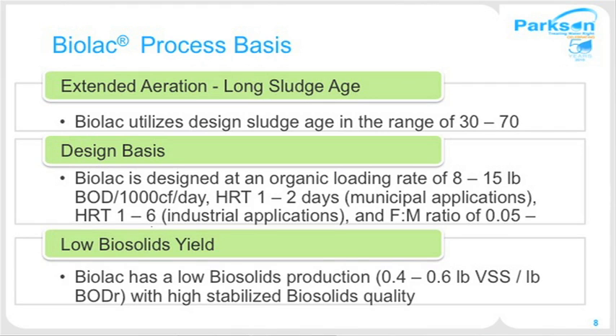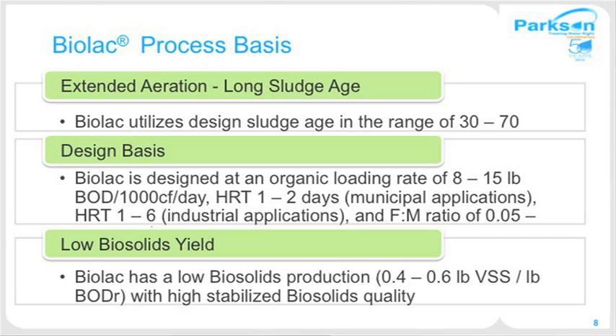The BioLac process has a low biosolids yield, which is a major advantage. It produces a yield of 0.4 to 0.6 pounds of solids per pound of BOD removed, making it an advantage over other processes.